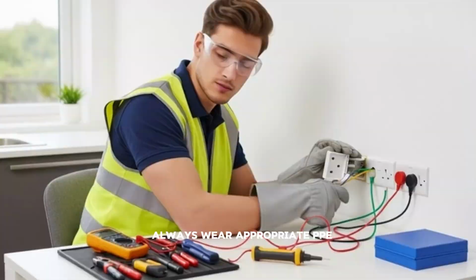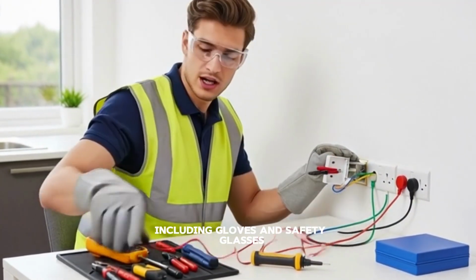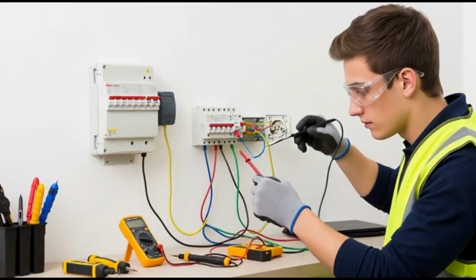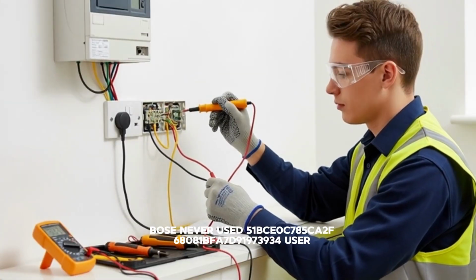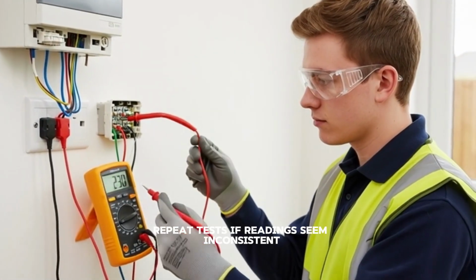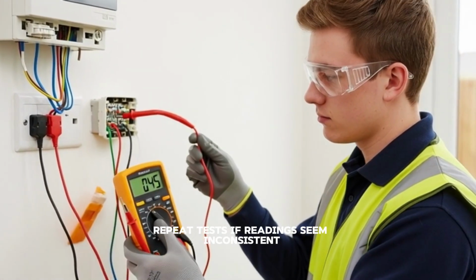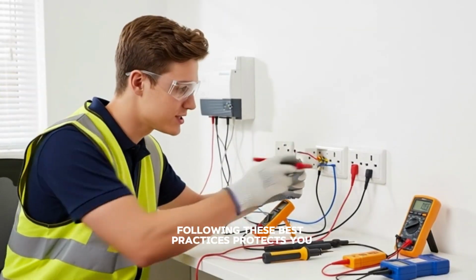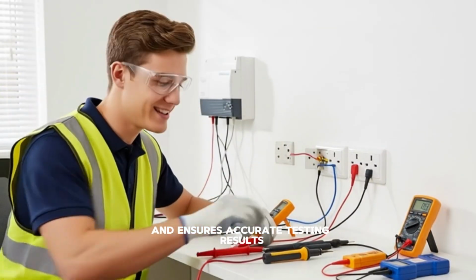Step 9. Safety tips and best practices. Always wear appropriate PPE, including gloves and safety glasses. Never bypass safety devices to complete a test. Double check that the circuit is isolated before touching any wires. Use calibrated, approved test equipment. Repeat tests if readings seem inconsistent. Following these best practices protects you and ensures accurate testing results.